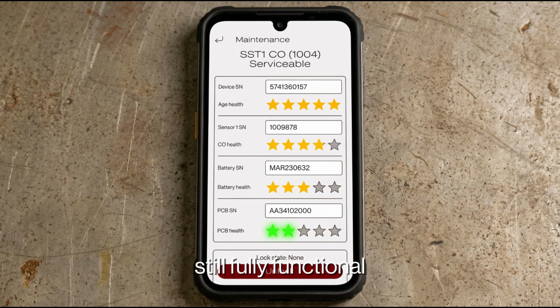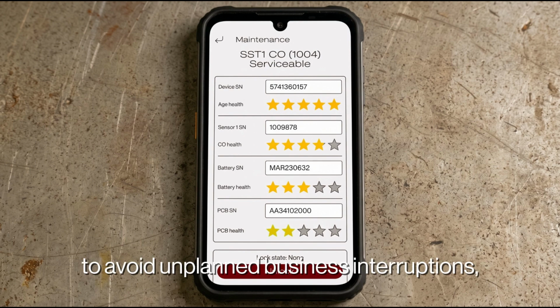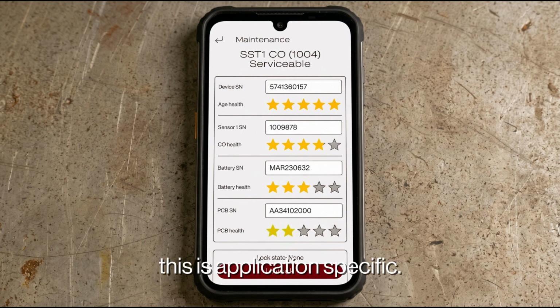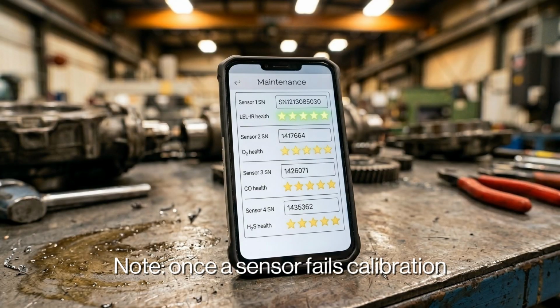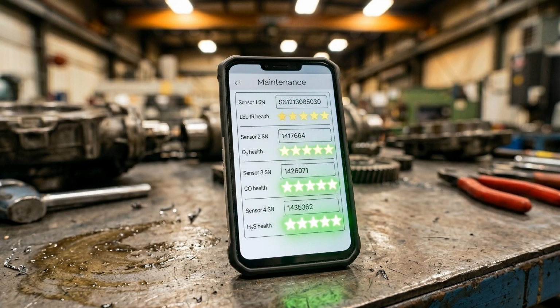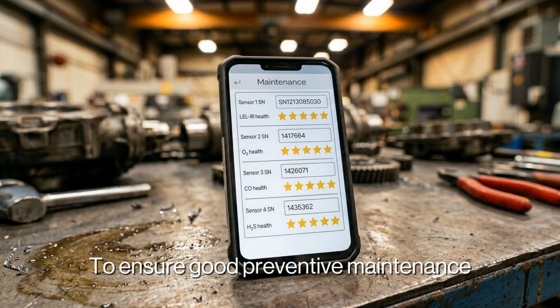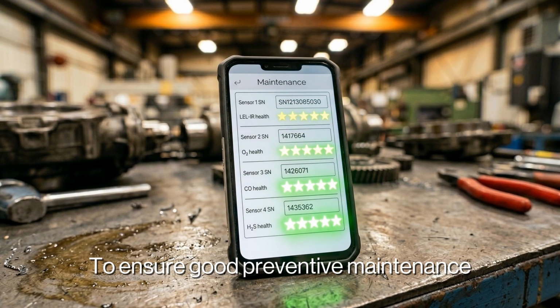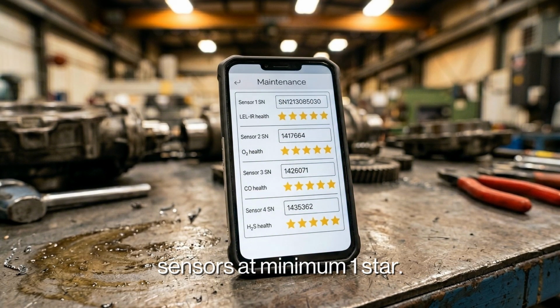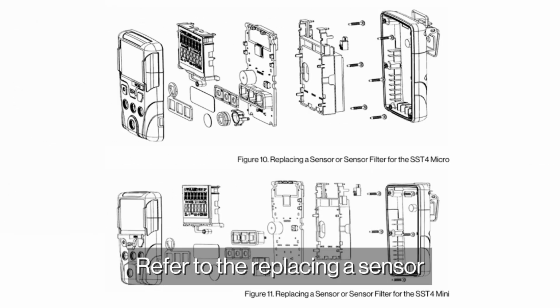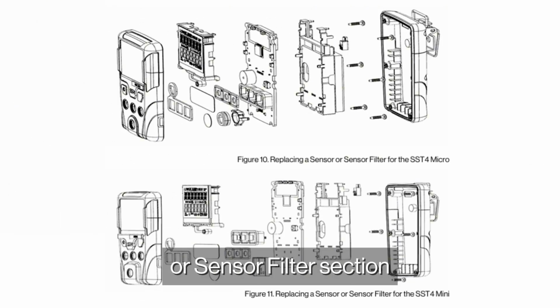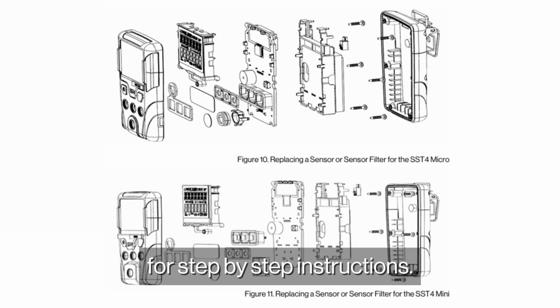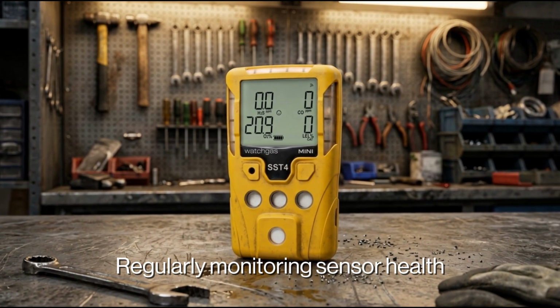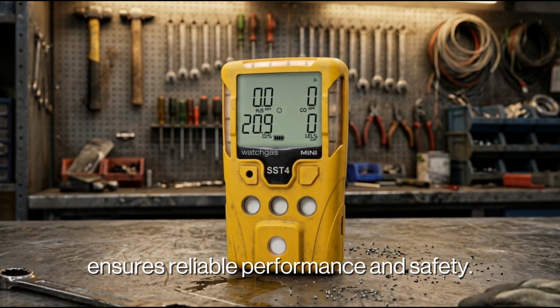fully functional, but should be flagged as potential sensor replacement in the near future to avoid unplanned business interruptions. This is application specific. Note, once a sensor fails calibration, it then needs to be replaced. To ensure good preventive maintenance, WatchGas recommends to replace sensors at minimum 1 star. Refer to the Replacing a Sensor or Sensor Filter section for step-by-step instructions. Regularly monitoring sensor health ensures reliable performance and safety.